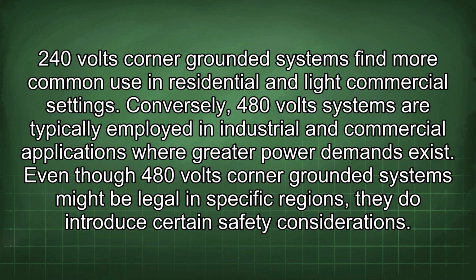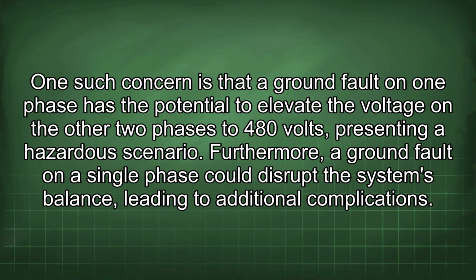Even though 480 volts corner-grounded systems might be legal in specific regions, they do introduce certain safety considerations. One such concern is that a ground fault on one phase has the potential to elevate the voltage on the other two phases to 480 volts, presenting a hazardous scenario. Furthermore, a ground fault on a single phase could disrupt the system's balance, leading to additional complications.